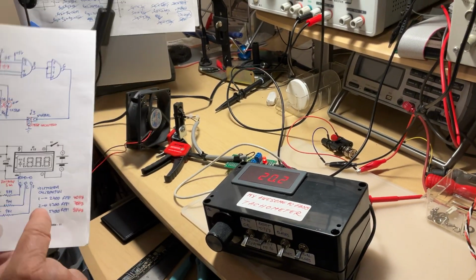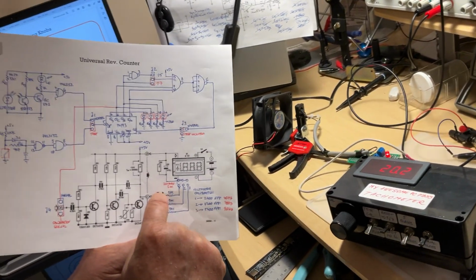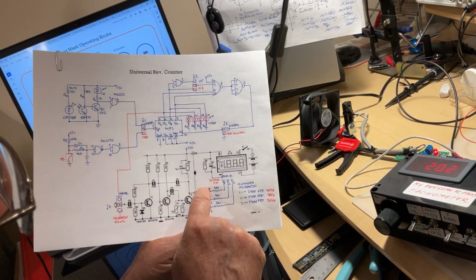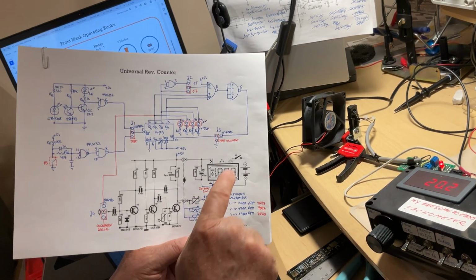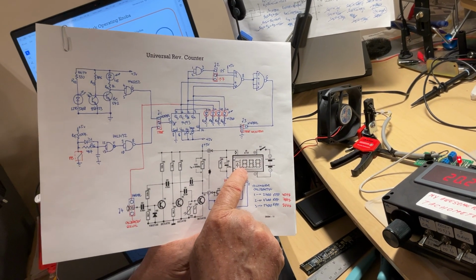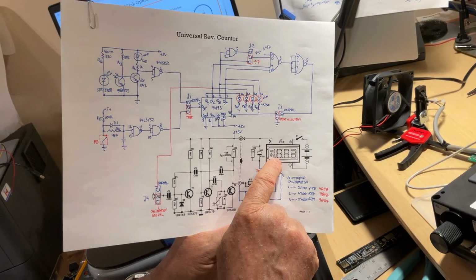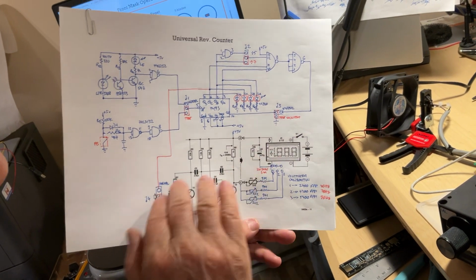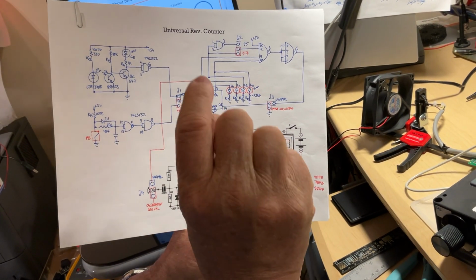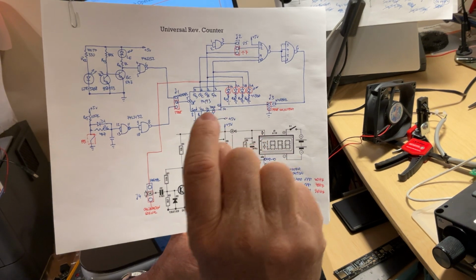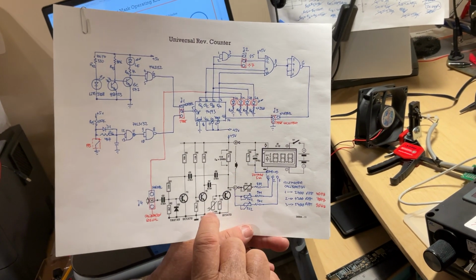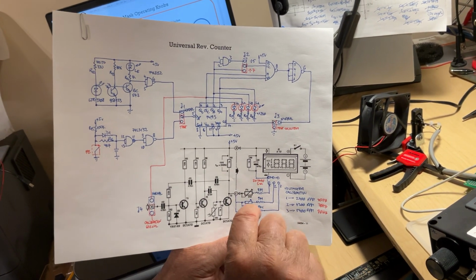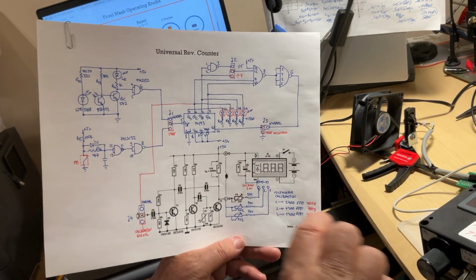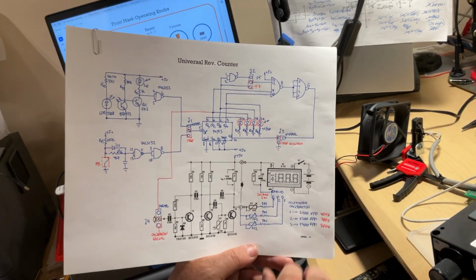On the detailed diagram, I used this to have 3 ranges for the calibration, just in case the industrial mini voltmeter you find isn't perfectly linear. So you split the range into 3, and for each one make adjustments to ensure the indication is right. But you won't need that - usually they're very good quality.